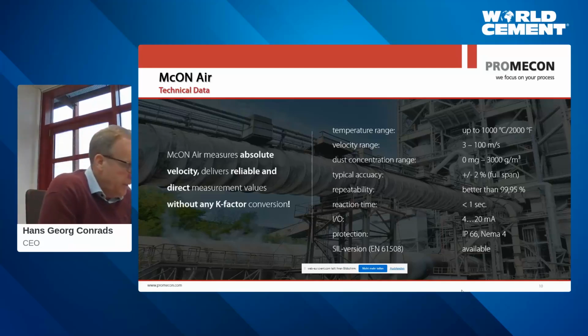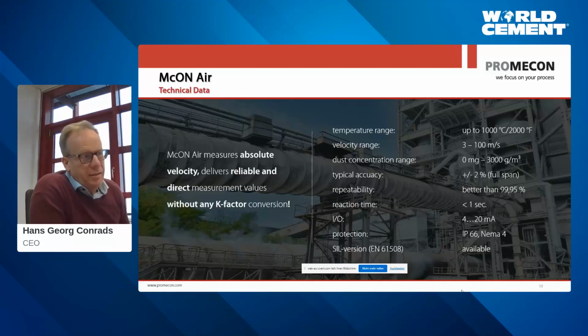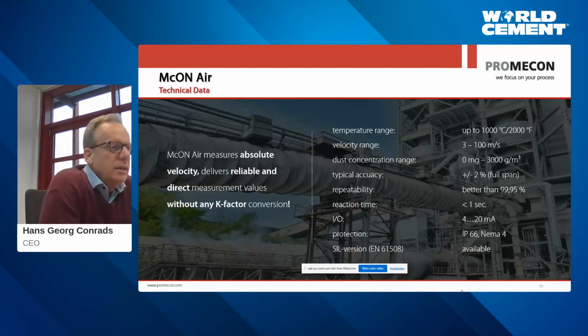If you have bends, then we have to analyze the situation, and maybe we have to put in 2 pairs of sensors so we can average what we see. So that's it on accuracy. Repeatability, I don't need to say much. It's way better than you will ever need. So the system will run with one calibration for its lifetime. There will be no recalibration for any of this. So it will simply go on forever.